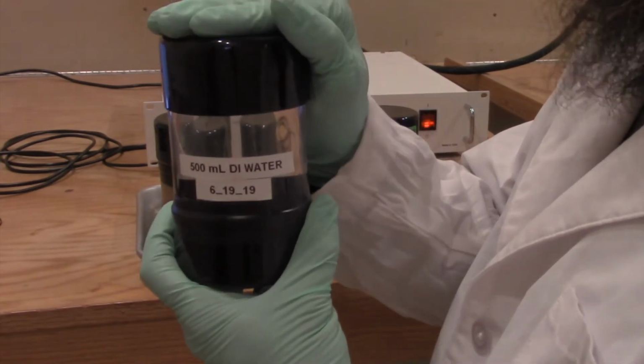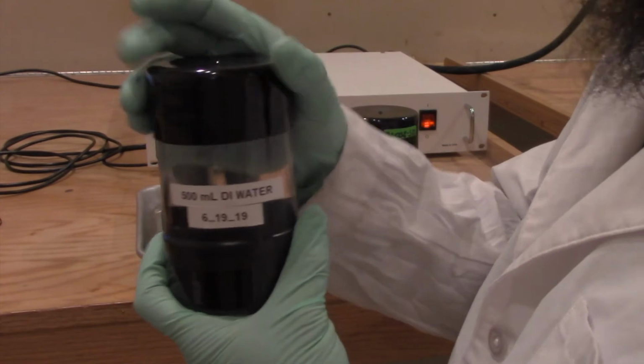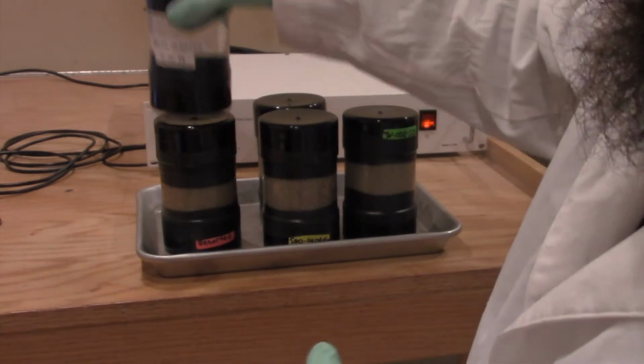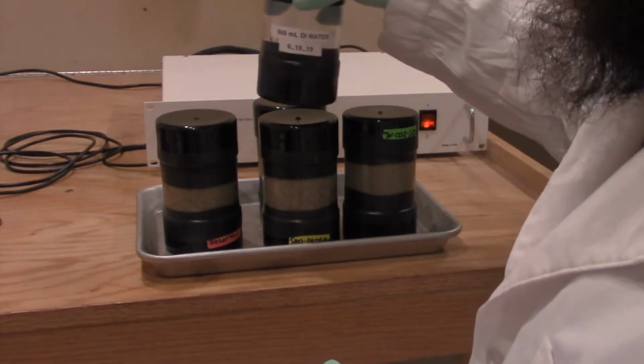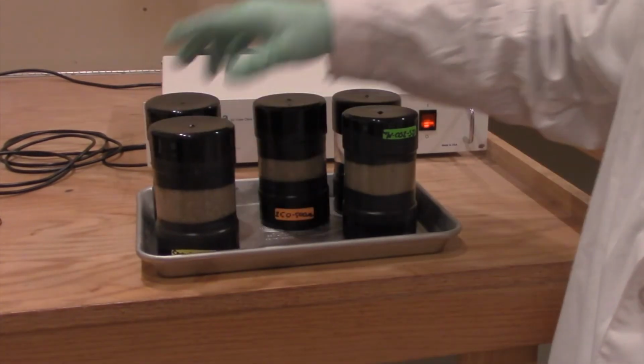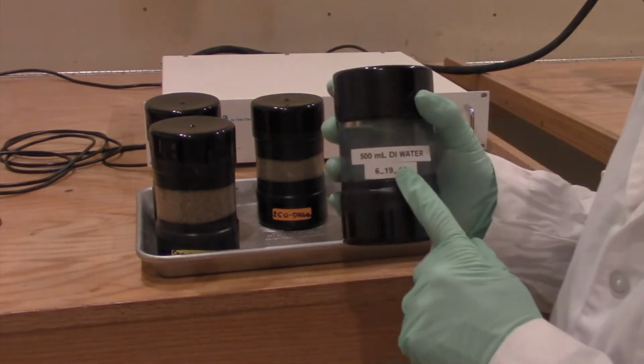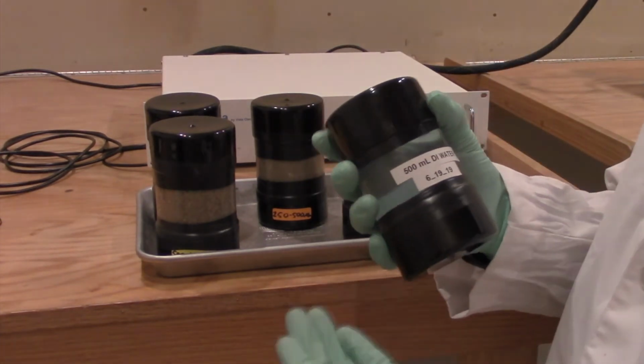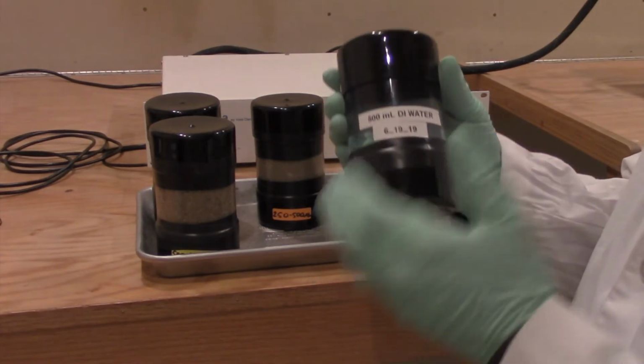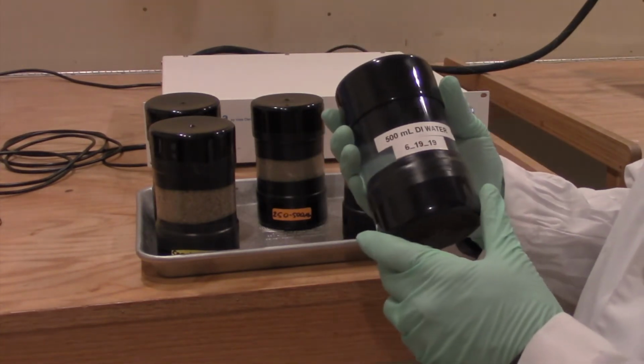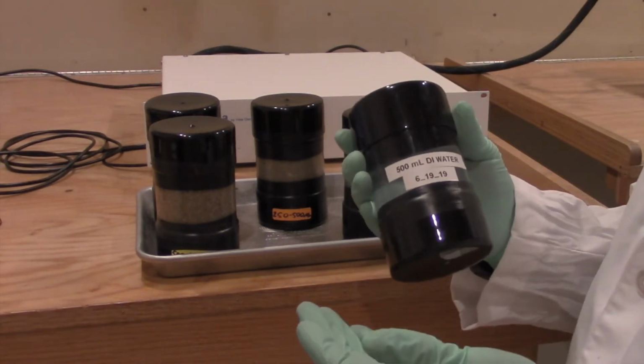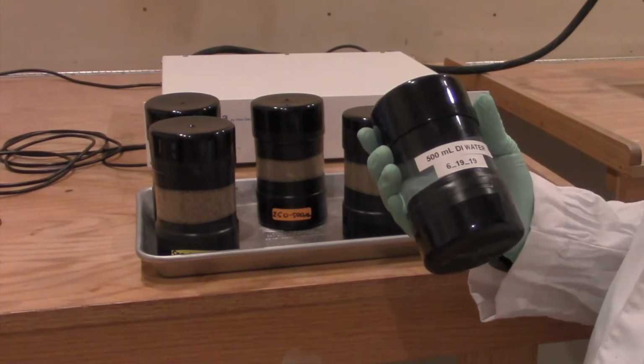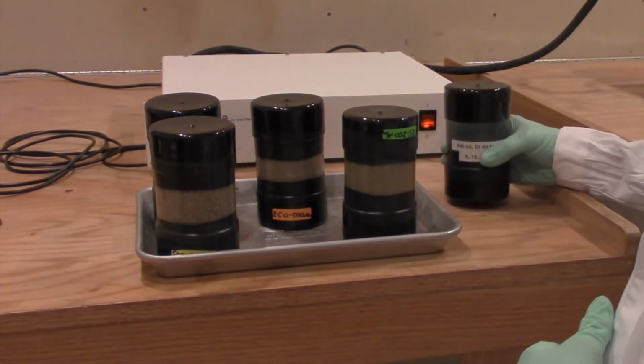All the sample holders are the same size. We use this calibration blank to set the instrument for the sample size. If you're using a different size sample, then you have to have a different size calibration blank. But these are all designed to be the same diameter and length, so they're the same sample volume. In order to make our measurement, the first step is to run the calibration blank, and that's going to give us the maximum signal intensity for that size sample. So we'll get a pure water signal, and we're going to do that by putting the sample in the instrument and measuring it to get that calibration measurement.